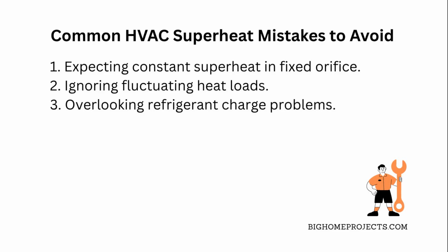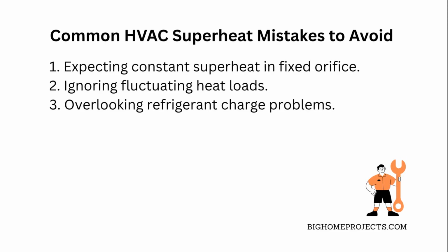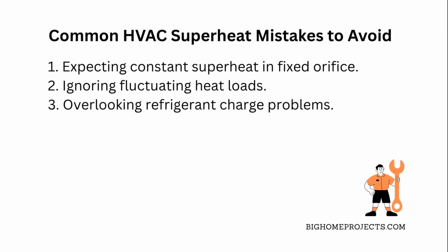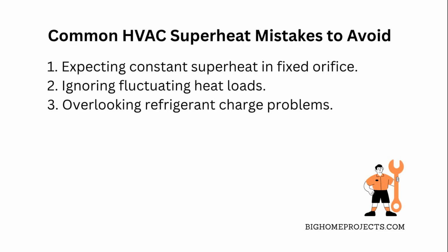To fix these, first, adjust your expectations and use superheat trends instead of single values. Next, take multiple readings under different loads to understand normal variations. Finally, verify refrigerant charge and inspect for physical blockages or leaks to keep everything flowing right.